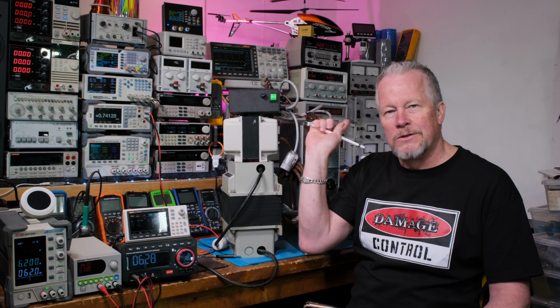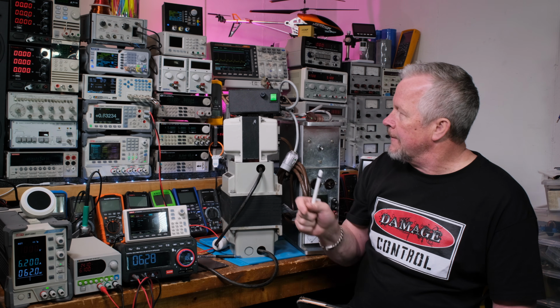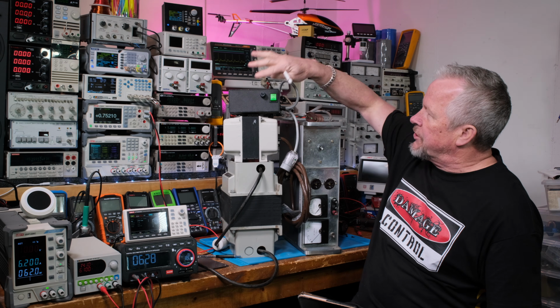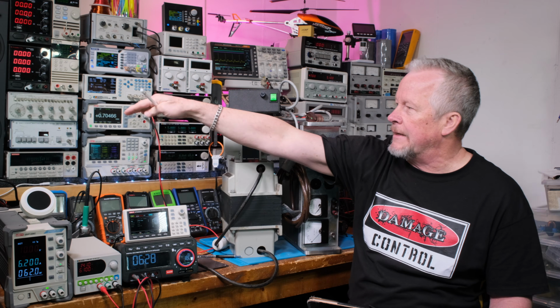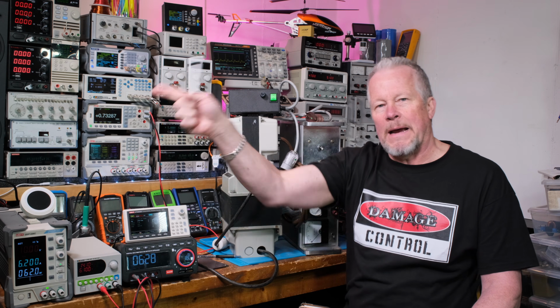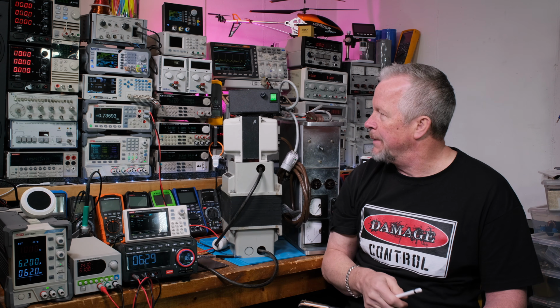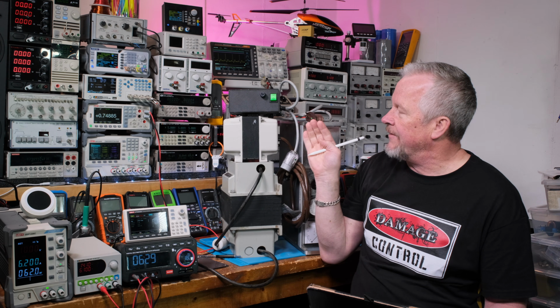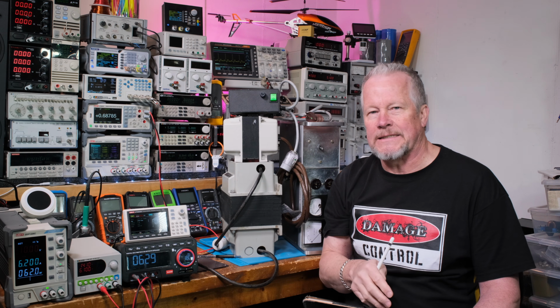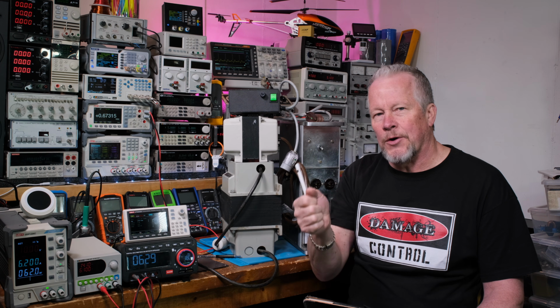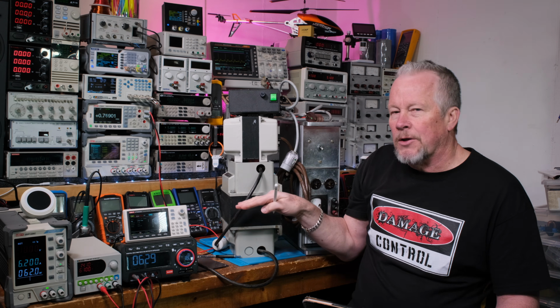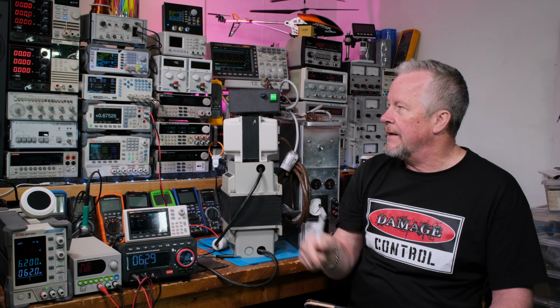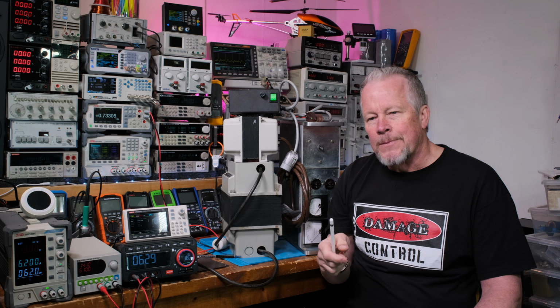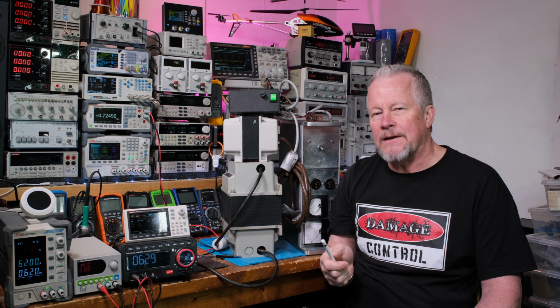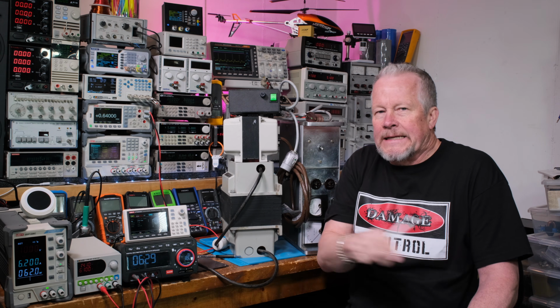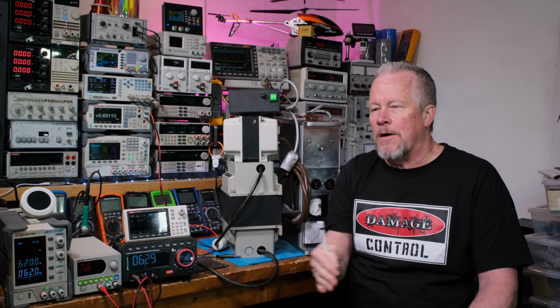The problem is if something over there is shorted to chassis, the line shorted to neutral, to the chassis over there, that high current can go through all these chassis connections, finally back to the neutral, and back to the breaker to pop it. But the problem is now you've got this heavy current flowing through all these chassis, instead of just jumping on a dedicated green wire and shooting back.